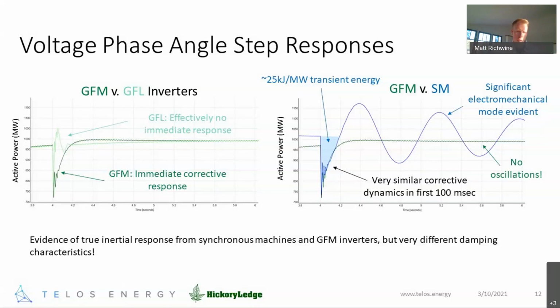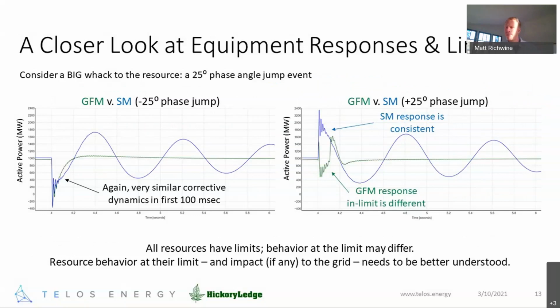Okay, now let's look at this, and I'll try to pick up the pace a little. Nick, jump in if there's anything I'm glossing over too quickly. We wanted to look at the phase jump event, and a bigger event in each direction, particularly zooming in on the grid forming versus the synchronous machine. On the left, again, the same type of event, but bigger, a bigger whack.